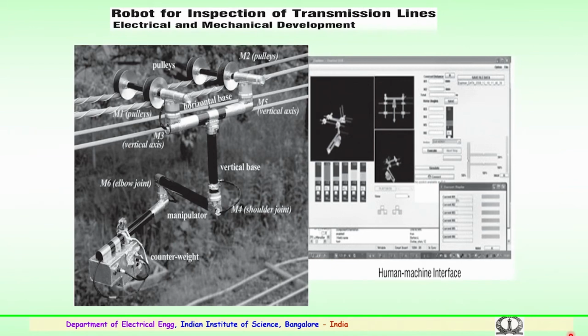Now, some important components, that is inspection tools for high voltage transmission, like the overhead conductors which are on the transmission towers. In case a few of the strands are damaged, or the conductor ages over a period of time, it requires maintenance. So for such needs, several tools have been developed, and at regular inspection or hotline maintenance, these conductor issues have to be rectified for the smooth transmission of power.